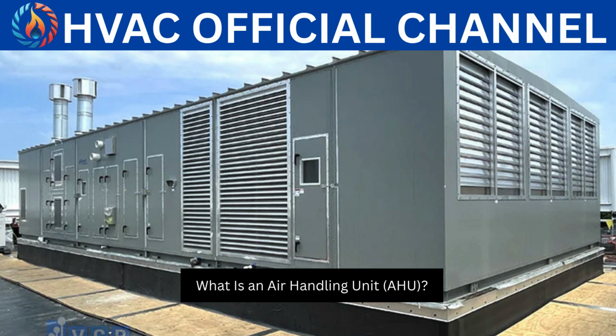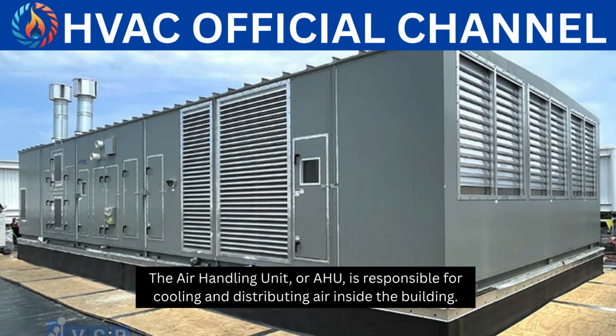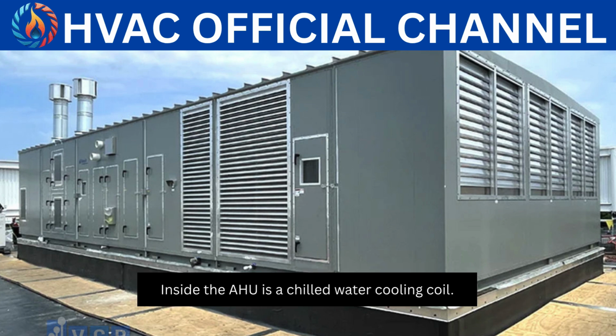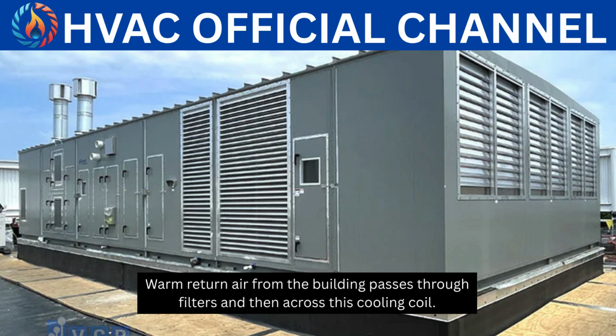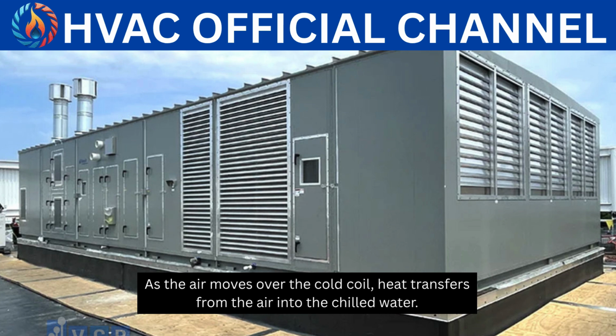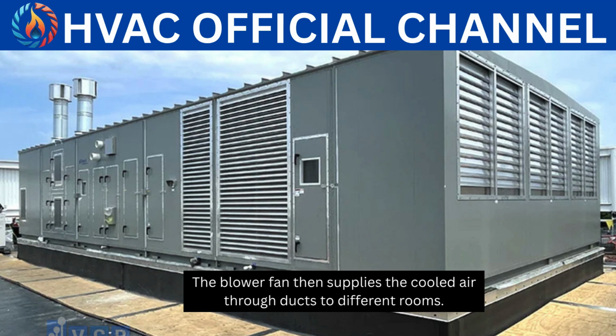What is an air handling unit, AHU? The air handling unit, or AHU, is responsible for cooling and distributing air inside the building. Inside the AHU is a chilled water cooling coil. Warm return air from the building passes through filters and then across this cooling coil. As the air moves over the cold coil, heat transfers from the air into the chilled water. The blower fan then supplies the cooled air through ducts to different rooms.